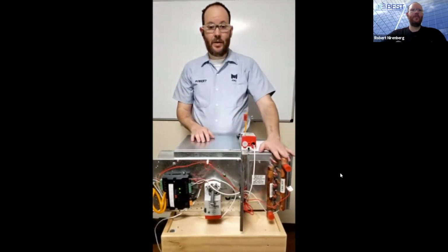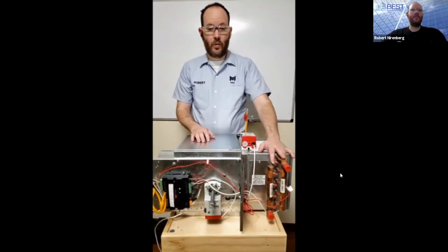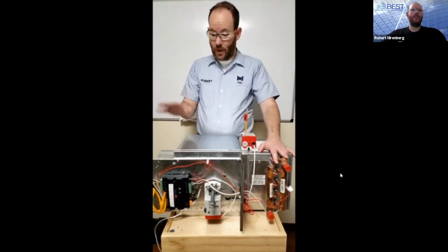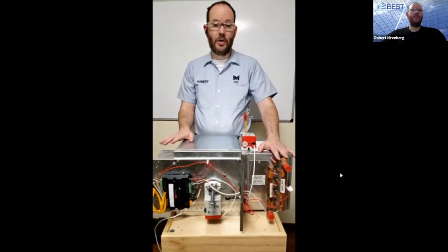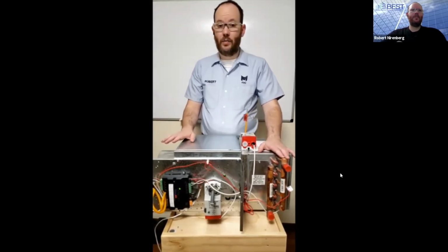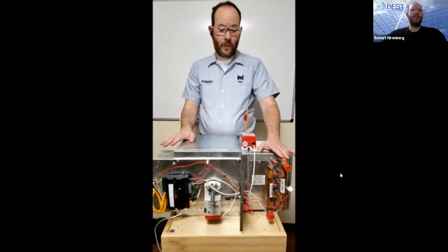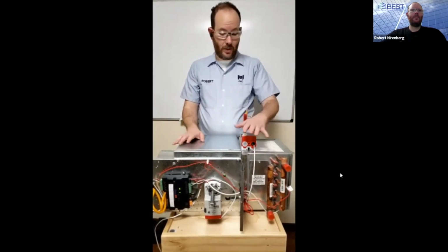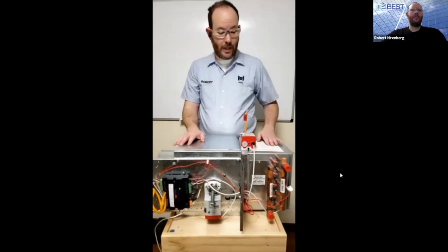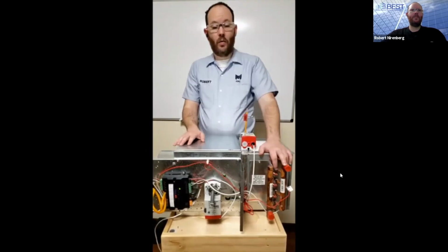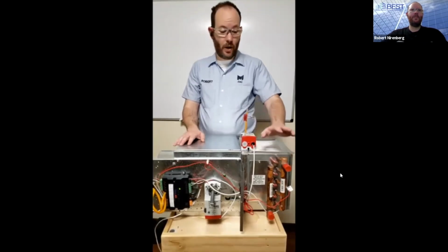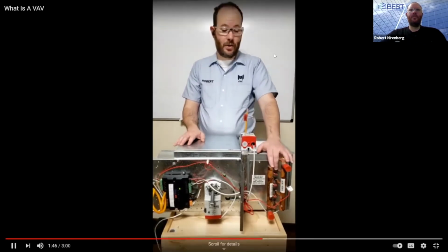Our reheat valve serves in combination with an actuator to add heat to the space when required, because our primary airflow is intended for cooling. So it is in most situations somewhere around 55 degrees, which gives us good cool air, which can effectively cool the space. When we need heat, we simply open up our valve to reheat using hot water, or in some cases steam, though hot water is the more common at this juncture in time, at least in the Midwest.